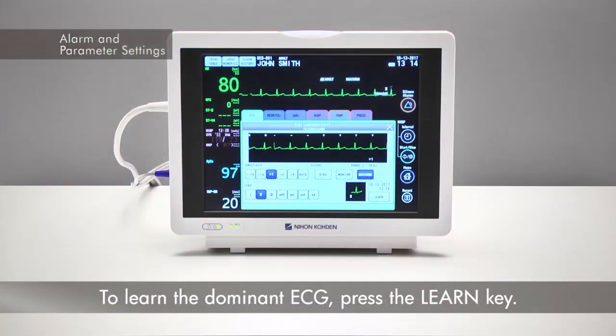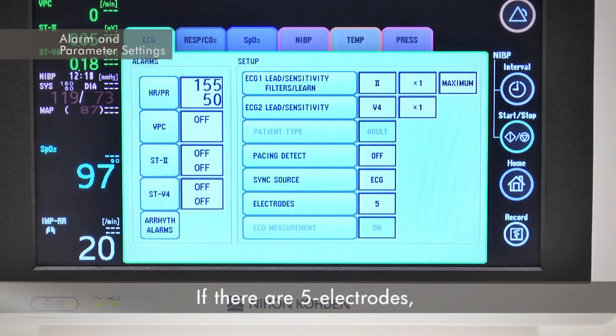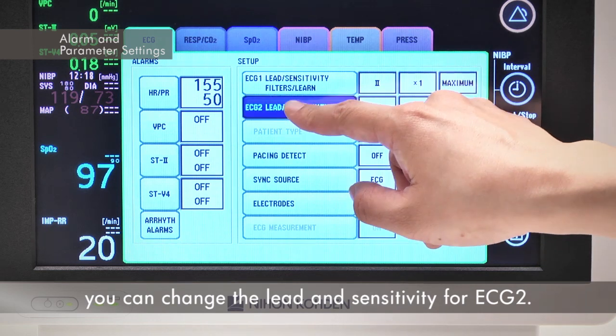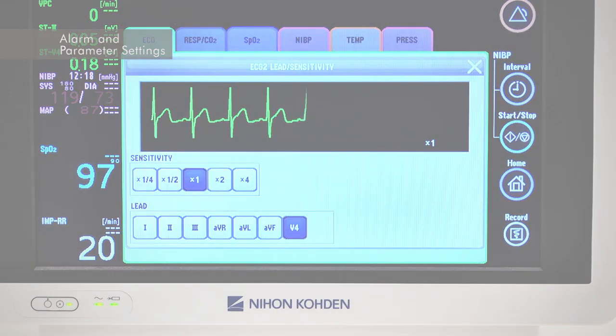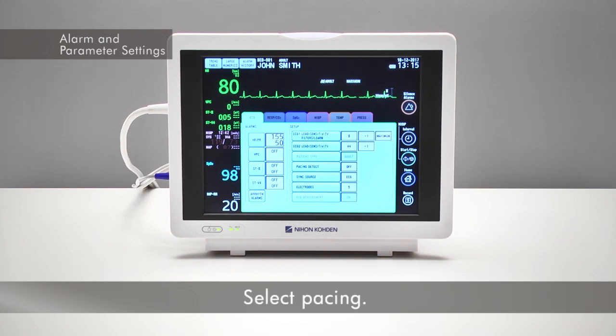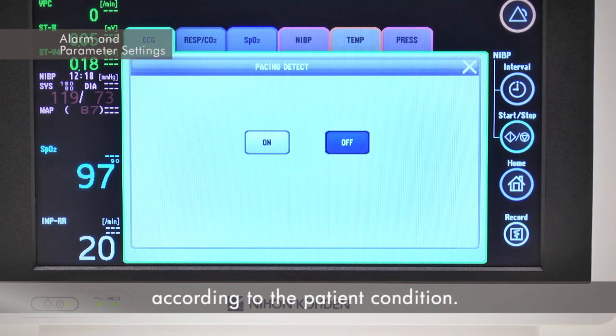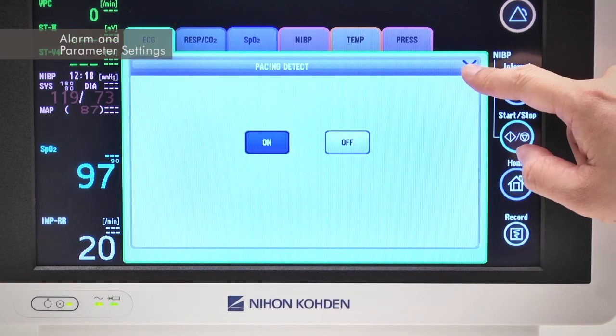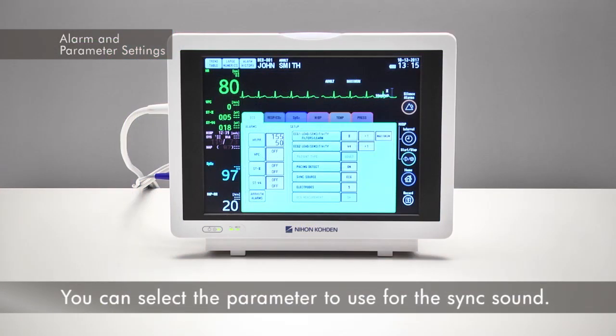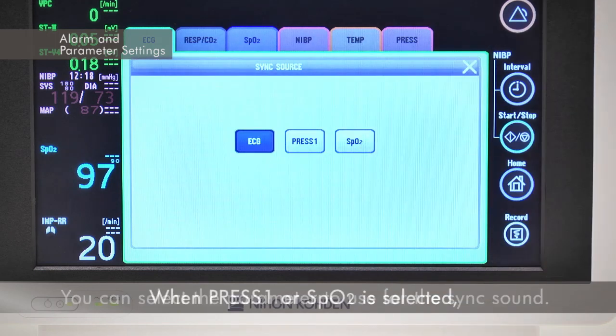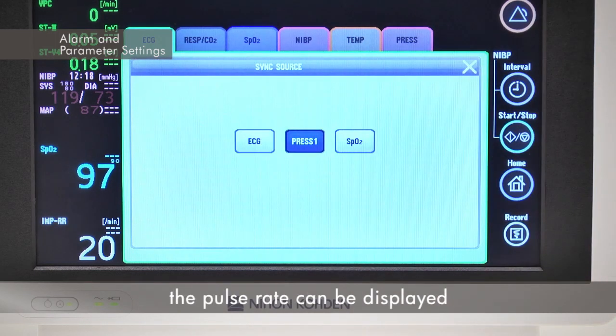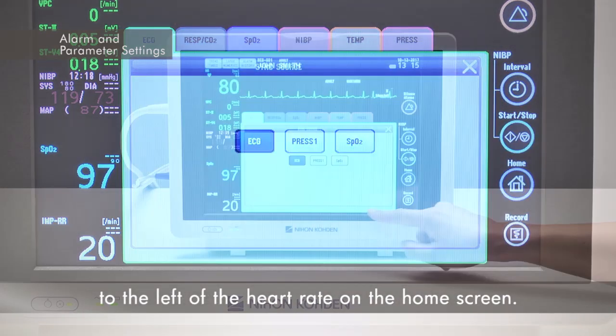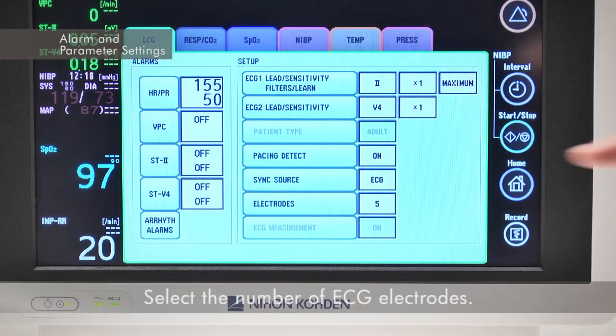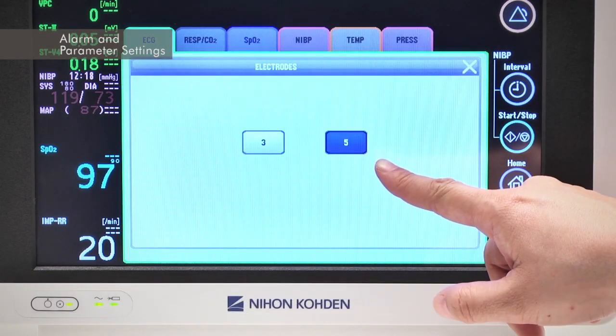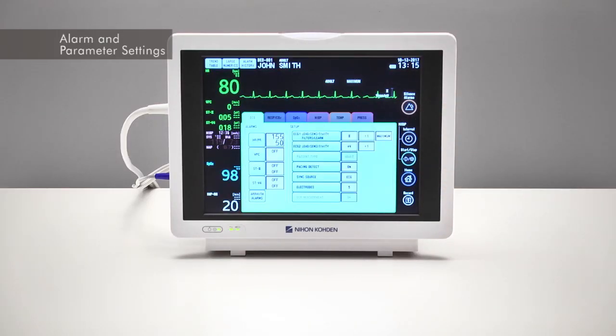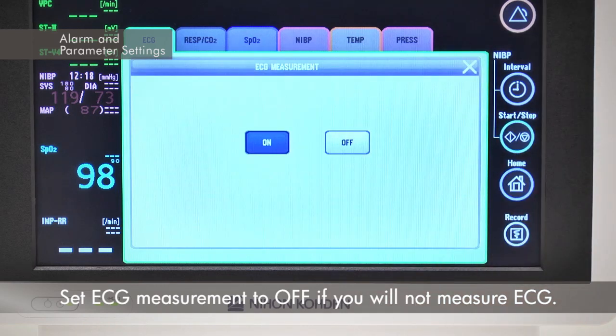To learn the dominant ECG, press the Learn key. If there are 5 electrodes, you can change the lead and sensitivity for ECG2. Select Pacing. You can turn pacing detection on or off according to the patient condition. You can select the parameter to use for the sync sound. When press 1 or SpO2 is selected, the pulse rate can be displayed to the left of the heart rate on the home screen. Select the number of ECG electrodes. Set ECG measurement to off if you will not measure ECG.